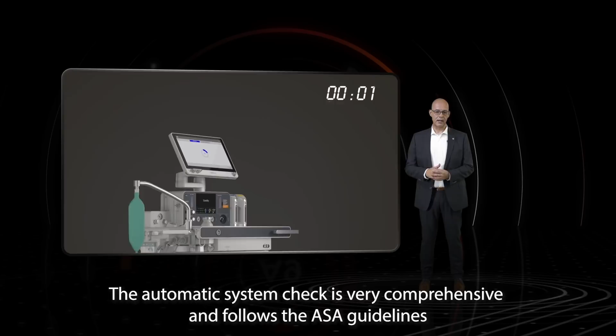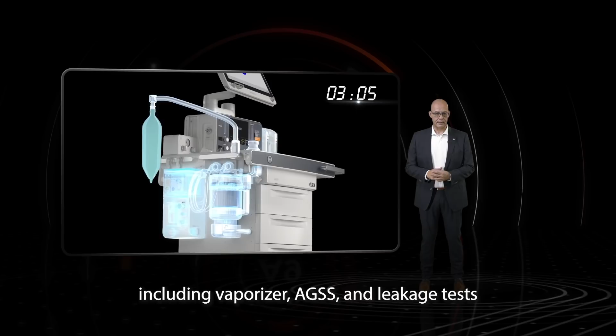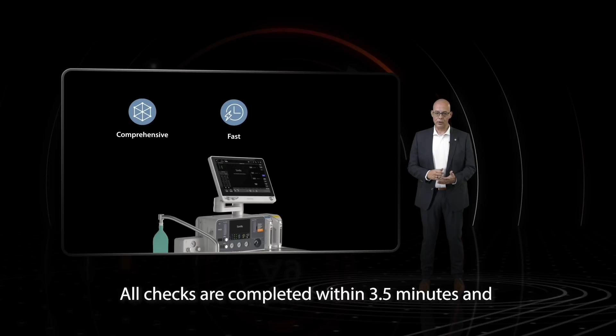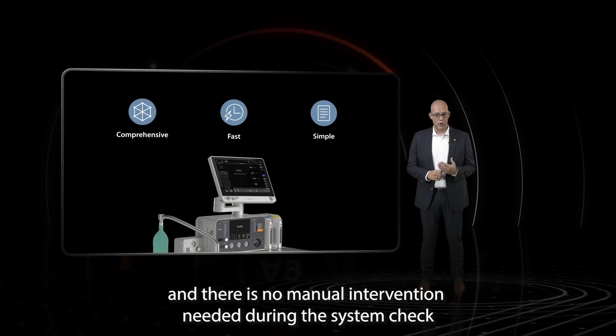The automatic system check is very comprehensive and follows the ASA guidelines, including vaporizer, AGSS and leakage tests, to ensure proper functioning. The test is fast, all checks are completed within 3.5 minutes, and the test is also simple and there is no manual intervention needed during the system check.